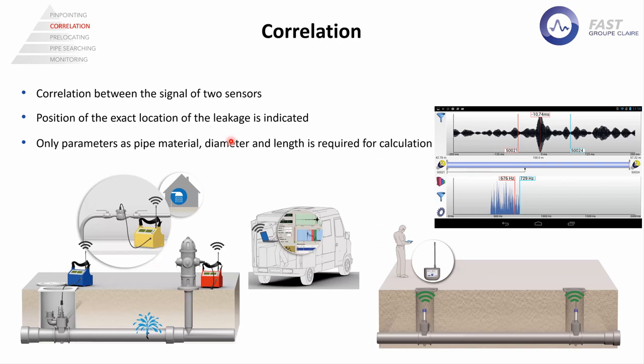Through a simple equation and calculation of the two signals, which is again a time deviation. The correlator only needs parameters like pipe material, diameter, and the length of the pipeline in order to show you the exact position of the leak.